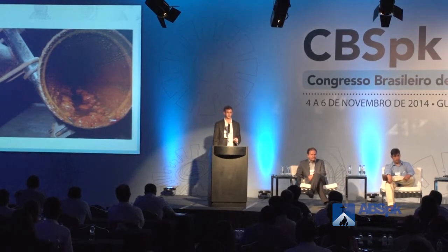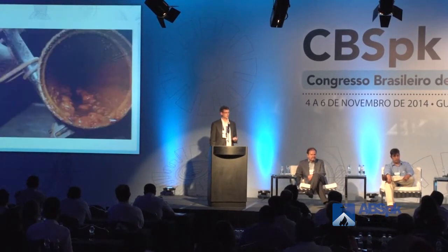So I have pictures as well of corrosion in fire sprinkler systems, things that we see in the United States. Here's an example of a wet system that I would consider a Class 1 corroded system. So essentially very little corrosion going on. As you can see in the next picture, as corrosion occurs more frequently, you start seeing larger corrosion deposits. This is something that would have to be replaced. If you opened up the sprinkler system and saw some corrosion going on, you need to replace that sprinkler pipe. And then you see things like this, where there's complete blockages of the fire sprinkler system, where no water would be able to flow. A system like this would have to be completely replaced.